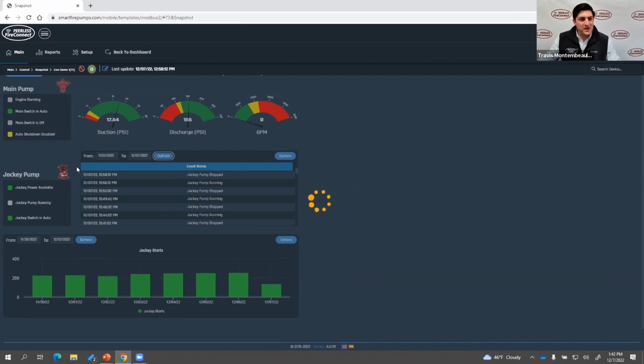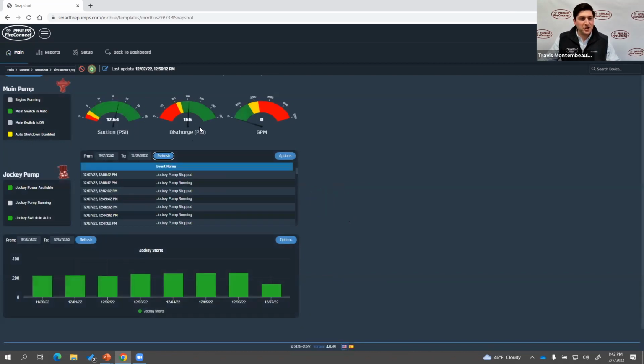While that's spinning, you can see on this snapshot page still, we've got suction pressure and discharge pressure, the event log, but on the sides here, you've got the core alarms that you pull out of the main fire pump controller. So engine running, main switch in auto versus off, and auto shutdown disabled. And then you've got jockey pump data, so power available and auto here. And at the bottom, you can see your starts over time. This jockey pump started 140 times today, 255 before that, 251 before that. So you get a little bit of a picture into that window here.